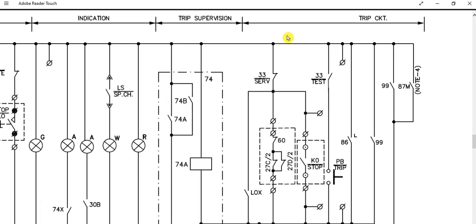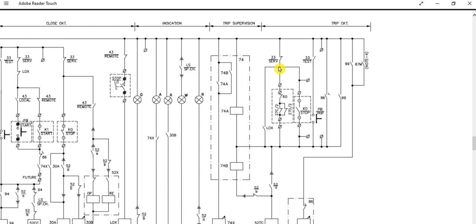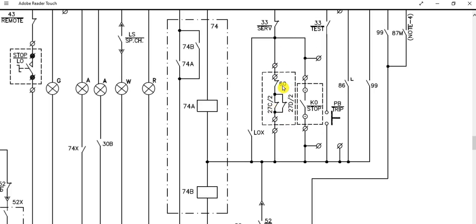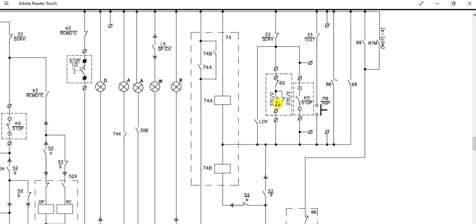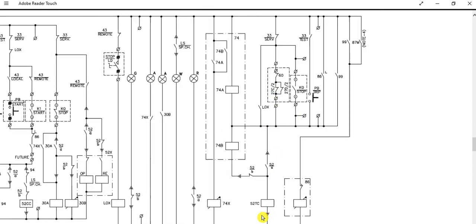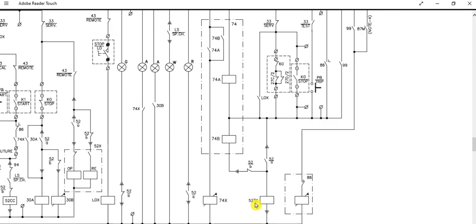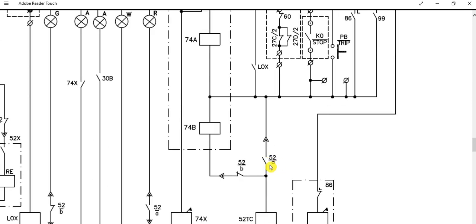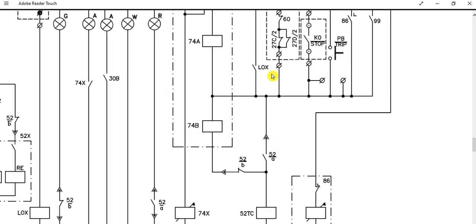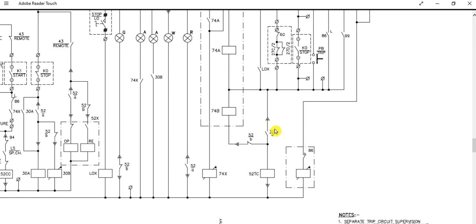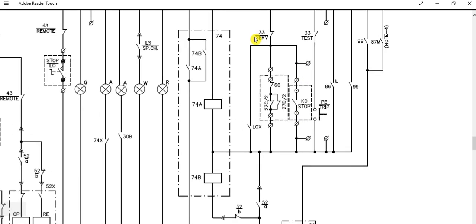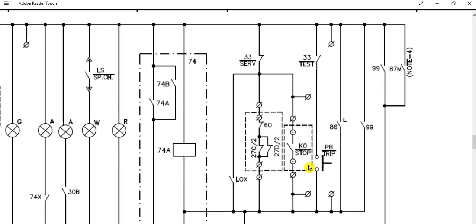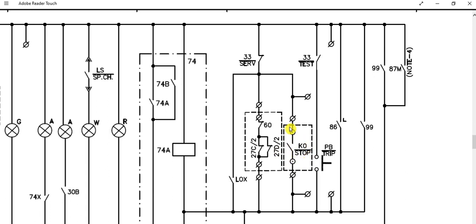Now this is the tripping circuit. Suppose the circuit breaker is in service position. This is the 60 DC circuit supervision relay — if that operates, or any under-voltage element operates, it will follow this path and energize 52TC, which is the trip coil of the circuit breaker. The 52A inner contact is in closed position before tripping the breaker, so this path is closed and the signal will pass through the trip coil. Also, if a stop command K0 is issued from DCS or PLC, it will also follow this tripping path.